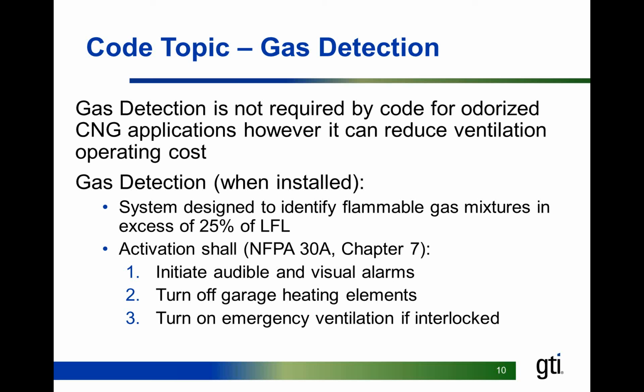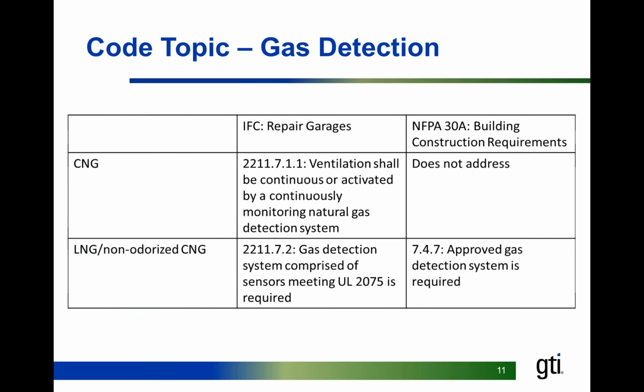And then there are some details on what that gas detection system needs to do and what the settings need to be. And this is a little more detail on where in the codes you can look to see what gas detection will affect and when it needs to trigger the ventilation system.